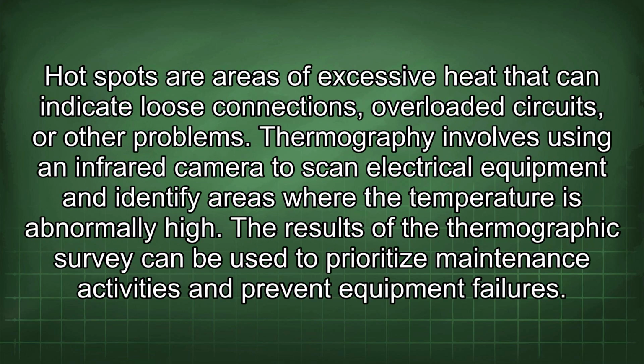Thermography is a non-destructive testing technique that can be used to detect hotspots in electrical equipment. Hotspots are areas of excessive heat that can indicate loose connections, overloaded circuits, or other problems. Thermography involves using an infrared camera to scan electrical equipment and identify areas where the temperature is abnormally high. The results of the thermographic survey can be used to prioritize maintenance activities and prevent equipment failures.